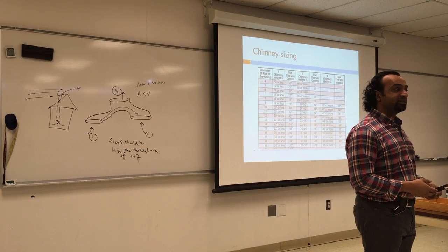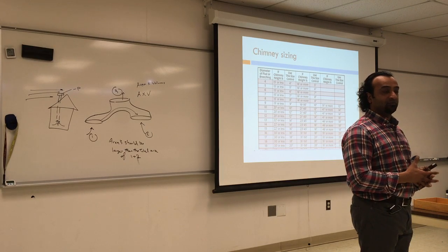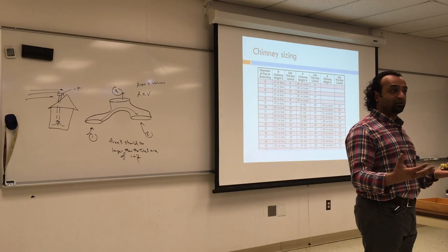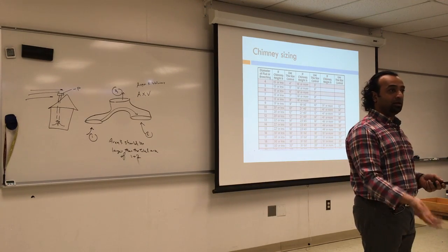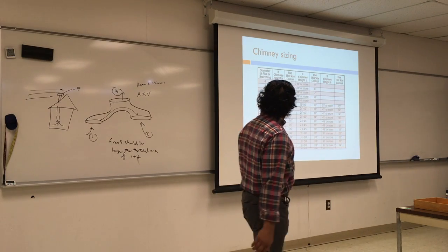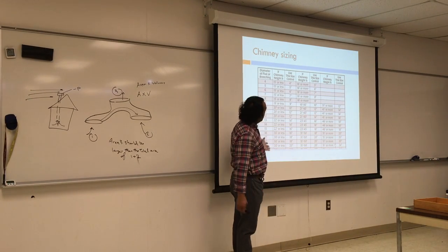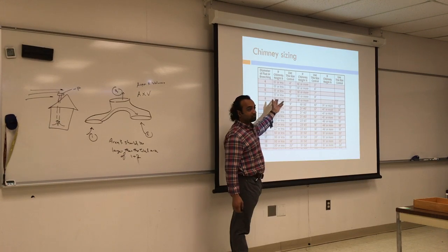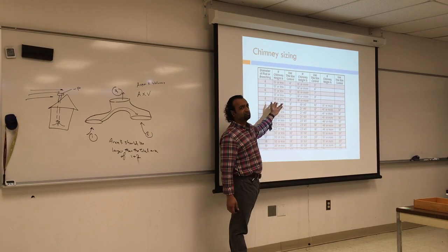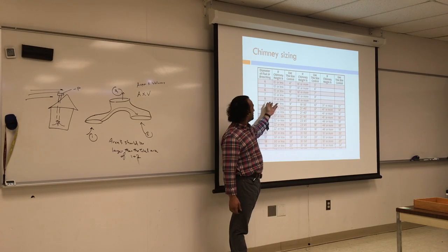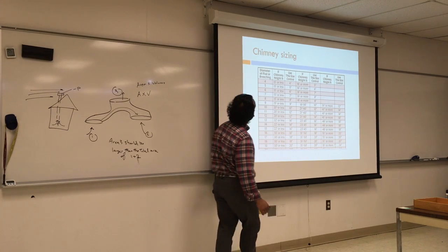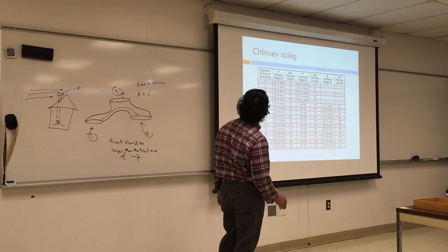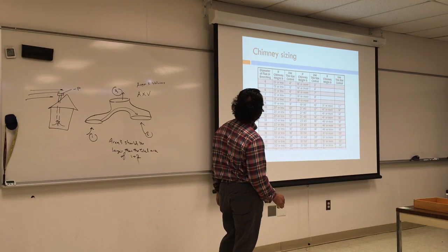And the chimney is made out of bricks. It actually lets go of a lot of heat. It gets cold, especially if you don't have a fireplace going to keep the air coming out. So this is something you want to look at and know that the length should not be too much. 15 feet is not that big, it's 2 stories. So probably in this case you have to either have a bigger one or do draft. Sorry, increase the size and have more flow.